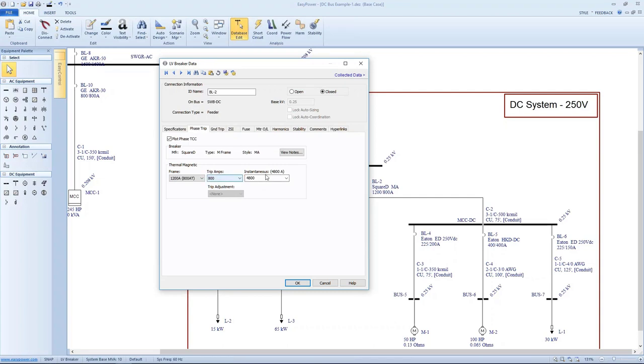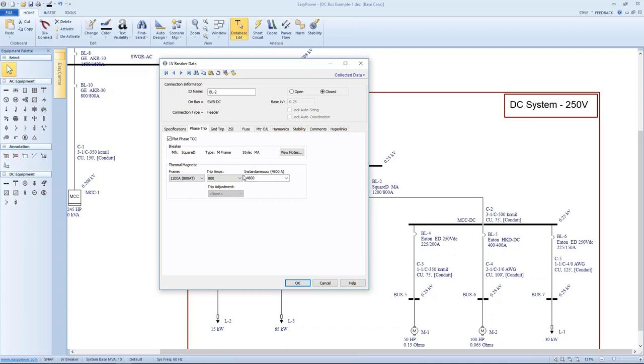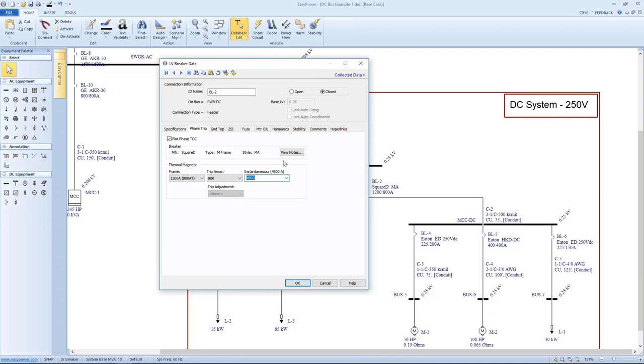Now, the significance here, and I want to just point this out briefly, is that the normal operations, operating current, in this case, we have an 800-amp trip point for this breaker. We have the ability, we have the need to identify a fault current that's much lower relative to the normal operating conditions of this breaker than we see in an AC side of the world. So normally, a molded case circuit breaker is set for a 10x trip point compared to what the maximum setting is for the breaker. In this case, we can see trip points set anywhere from 5, 4 or 5x, the load current, up to 10 times. So that can make the situation a little bit more complicated in terms of trip time.